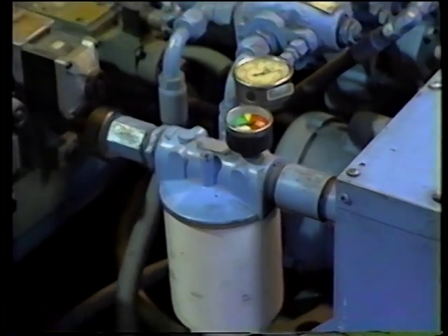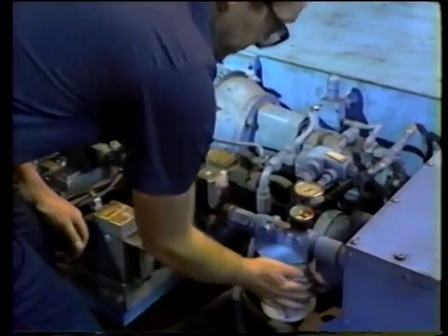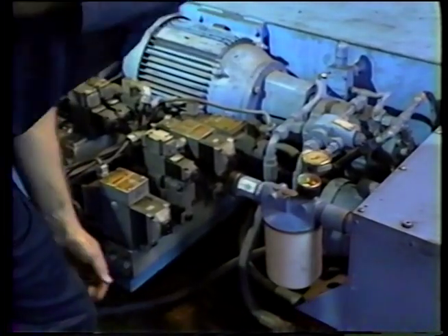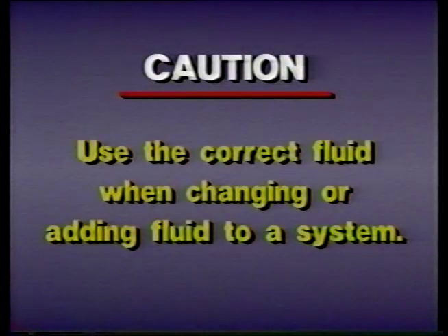Inspect your system's fluid frequently for contamination and keep any filters serviced regularly. If the filter is being bypassed, it needs to be cleaned or replaced. One final note of caution. Make sure you're using the right fluid when changing or adding fluid to a system. Because different additives may have been used, different brands of fluid may not be interchangeable.